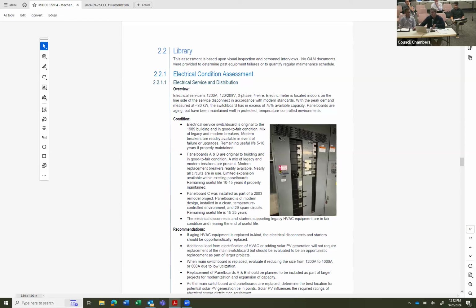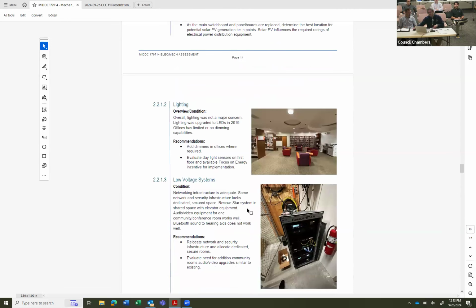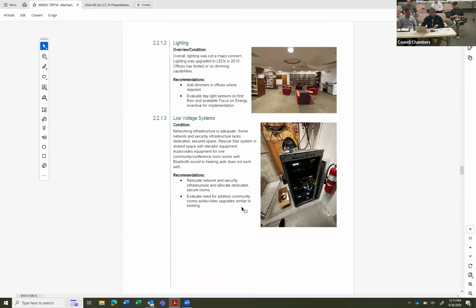Whereas the level 3 that was looking at more of the geothermal aspect would have a lower increase in electrical load. And then another aspect to the electrical infrastructure, when you're looking at, say, adding your solar photovoltaic solution to this, is that it is considered an additional source of incoming power. And so, not to get too complicated here, you have to make sure that your incoming switchboard can handle the existing utility feed and also your photovoltaic energy that's coming through there. So that infrastructure did have the capacity to account for that. And you may need to make some adjustments on the utility protection end of it. But in summarizing all of it, it does have the capacity and ability to support the increase in electrical load, as well as if we look at photovoltaic or other solutions of that nature.